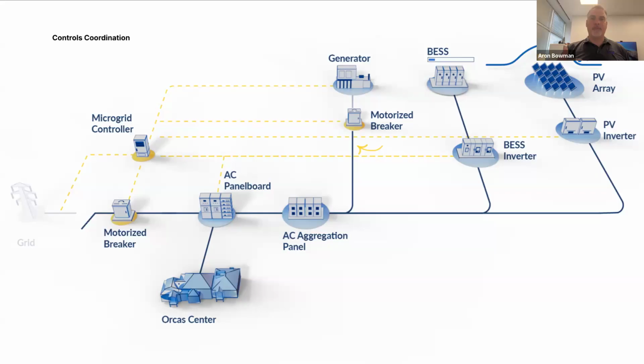So we're monitoring voltage and frequency from the grid. And we have set points in there so that if we see the frequency dip, we'll bolster that with the BESS to stabilize the grid at the facility, or even go offline from the grid because the frequency is so ugly or the voltage is so ugly from the grid. There are different settings that we work with in different regions, and different utilities have different variations. But then in that off-grid situation, talking about bringing the generator up, our mode of operation from an ELM microgrid control standpoint is to keep the generator happy.